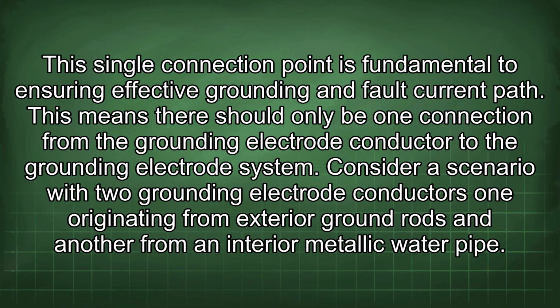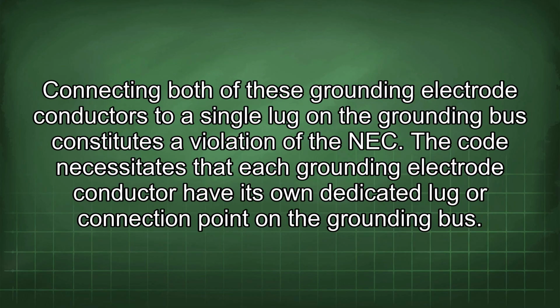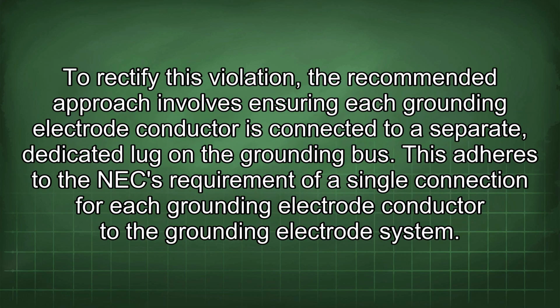Consider a scenario with two grounding electrode conductors, one originating from exterior ground rods and another from an interior metallic water pipe. Connecting both of these grounding electrode conductors to a single lug on the grounding bus constitutes a violation of the NEC. The code necessitates that each grounding electrode conductor have its own dedicated lug or connection point on the grounding bus. To rectify this violation, the recommended approach involves ensuring each grounding electrode conductor is connected to a separate dedicated lug on the grounding bus. This adheres to the NEC requirement of a single connection for each grounding electrode conductor to the grounding electrode system.